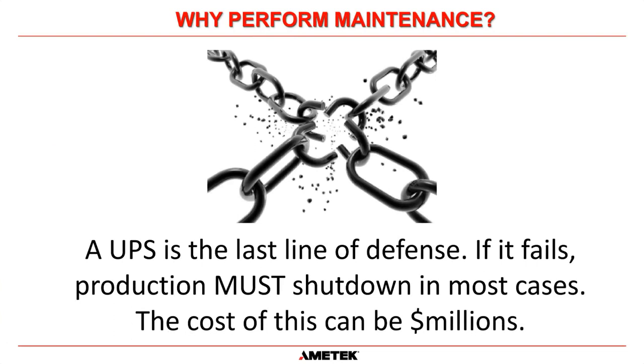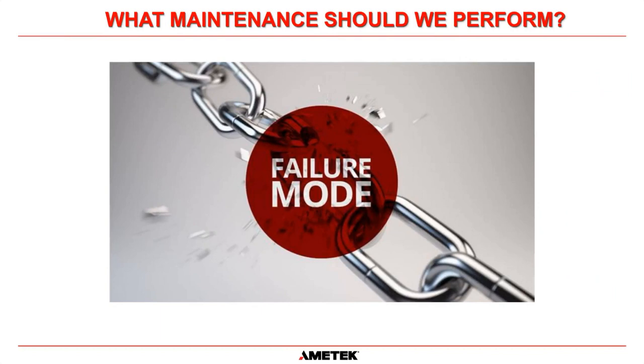And as I mentioned before, remember, the UPS is the last line of defense. Everything connected to a UPS is critical. That's why it's connected to a UPS. So if the UPS fails and there's no bypass, if it just completely crashes, then production must shut down in most cases. All of your fail safes will come into place and everything will shut down in your production process. And that can cost millions of dollars. So we want to prevent that as much as we possibly can. So what are the failure modes? You know, what maintenance should we perform with regards to what type of failure modes that we see in big industrial electronic equipment?